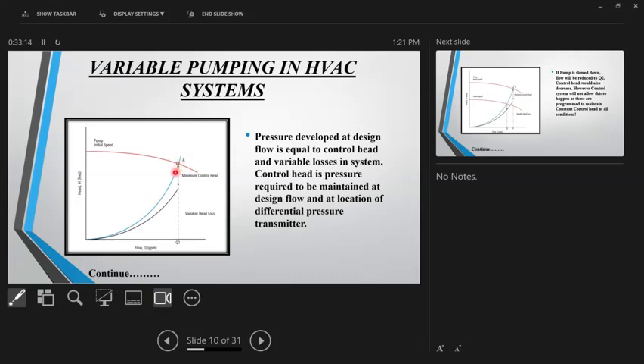Now, if you resolve this system curve into two components, one is a variable loss. Variable loss means the friction loss, or variable head loss, which is proportional to the flow. So you resolve this blue line into two components: one is a fixed head, the other is a variable head. What is fixed head? We'll see later. Don't worry much about this at this point. Let us concentrate on variable head. It is very simple to understand that if the flow increases, the variable head increases. It's actually again a parabola.